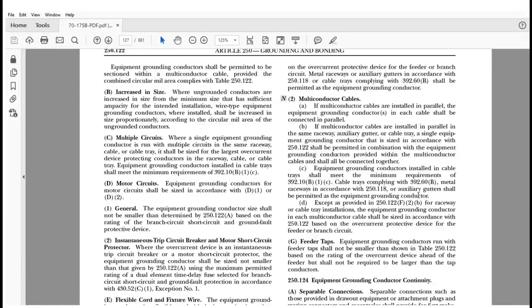Okay, what it's saying is, look, like what I just said earlier, except here where it gives you a bone, it says for raceway or cable tray installations, the equipment grounding conductor in each multi-conductor cable shall be sized in accordance with 250.122 based on the overcurrent protective device for the feeder or branch circuit. So again, if you don't meet this provision right here, then just like I said earlier, you're going to have to make sure the MC cable or other multi-conductor cable that you purchase has a full-sized equipment grounding conductor for that parallel intent. Okay, you can't use an off-the-shelf one. You understand what I'm saying here? Hopefully you get it. That's what it says here. It says, hey, I'll let you do this.